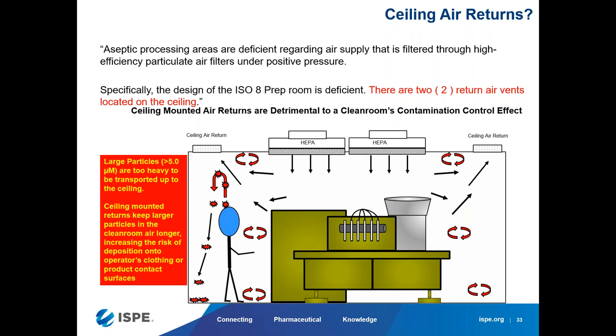And luckily, the client caught it and said, we think there's something off here. They wanted a sterile sampling booth in an ISO 8 room. But the ISO 8 room had ceiling returns, and the sterile sampling booth had negative pressure. That means anything from outside can go inside the sterile sampling booth. Sealing returns, all 5 micron particles at work level, and the negatively pressured booth sucks them in there. They could have never made any transfer of sterile sampling at all.